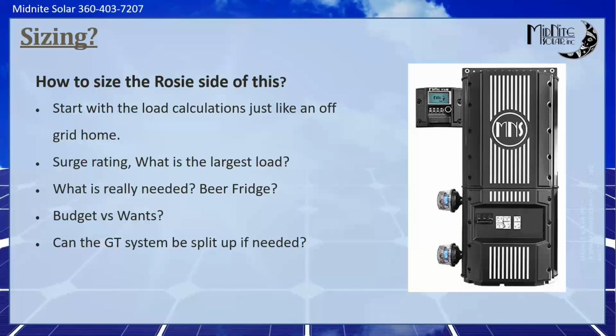And once you know the size of the system based on that information, like what do they need, what do they want, then we have to look at the grid tie system, because the grid tie system does play a part in this sizing. So let's say that same customer has a 15 kilowatt grid tie inverter, or 14. Let's say 14 kilowatt. That's an easier number. Then it's a single inverter. The only choice we have is 2 Rosies, because we have to follow that 1-to-1 ratio, which we'll talk about a little bit more.